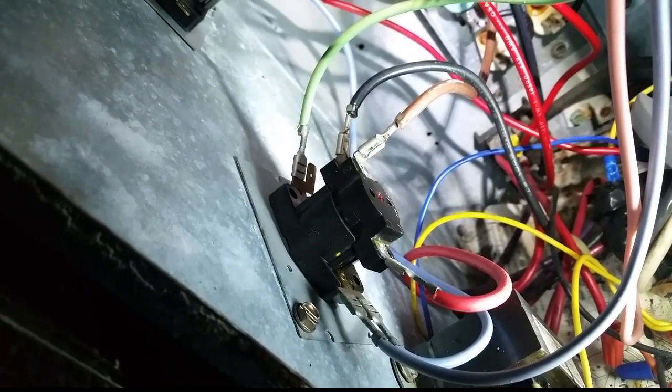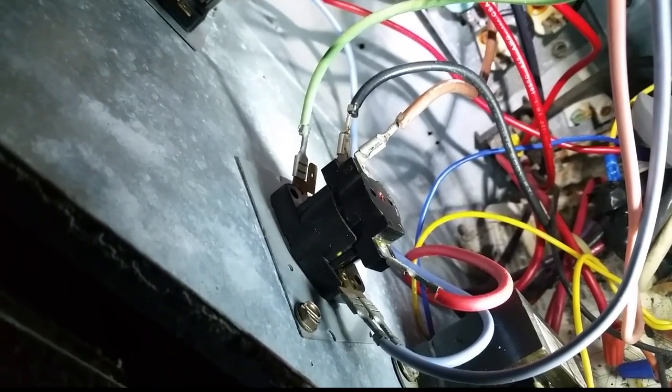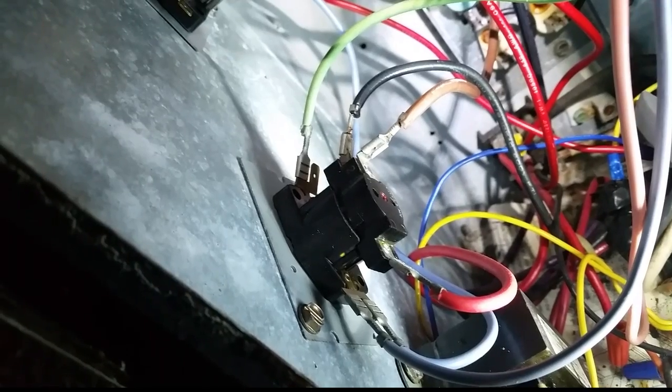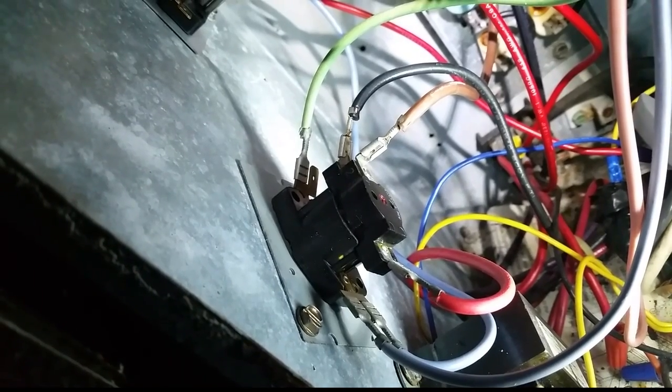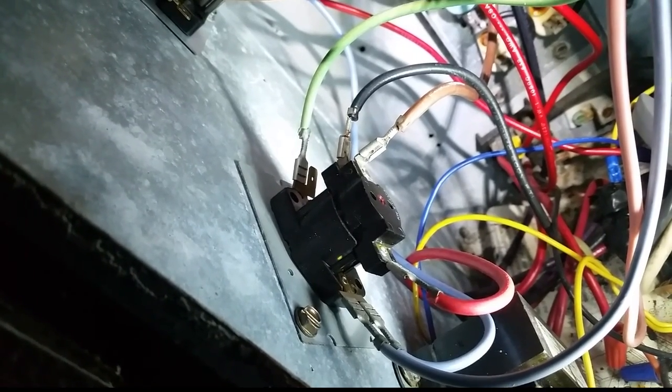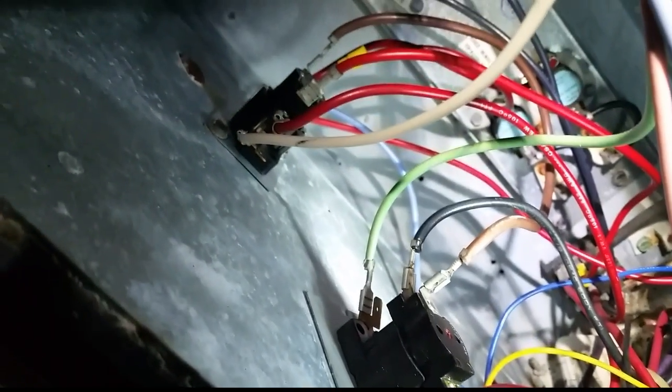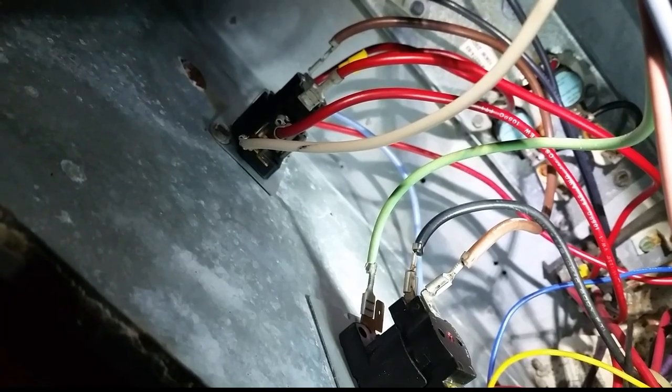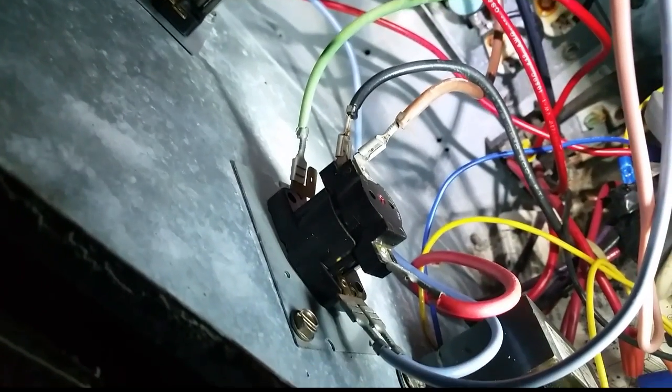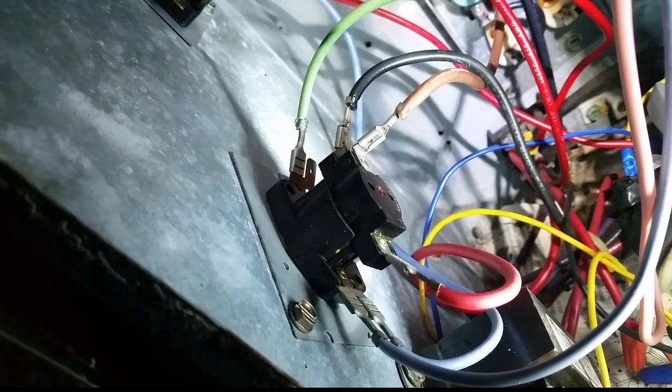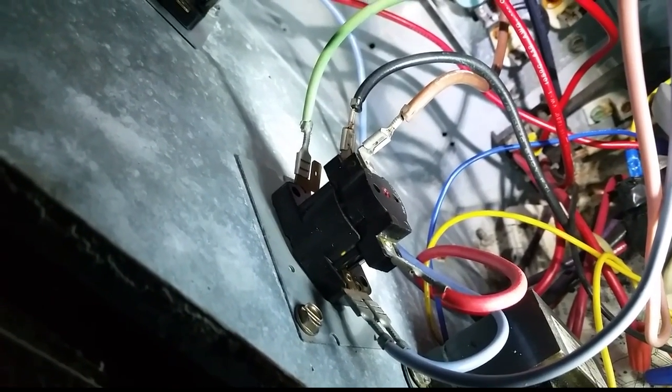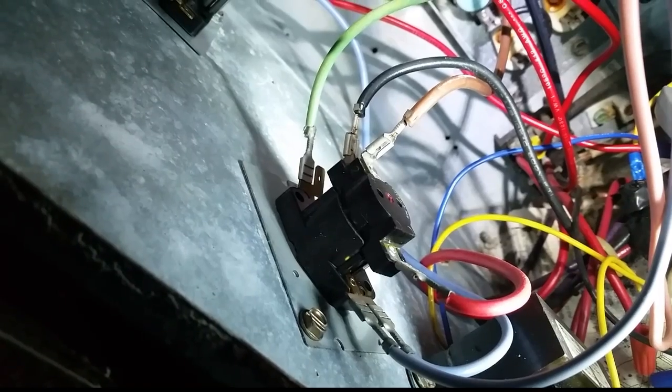But if there's no power to the base, the black and brown form a normally closed circuit. So if the heat strips energize through the sequencer, it'll send power over here through the brown and then send power to the fan motor on the black.